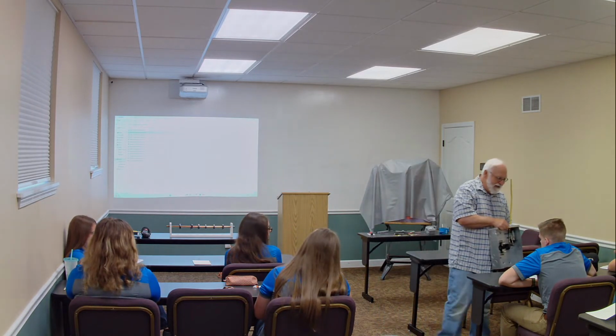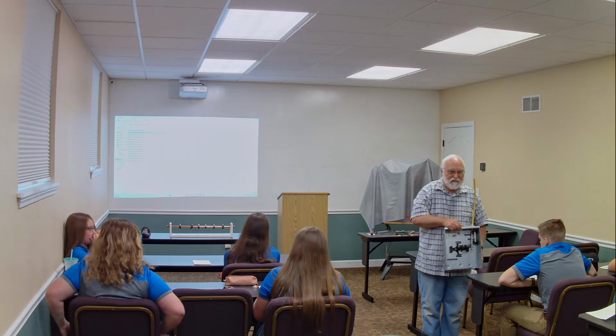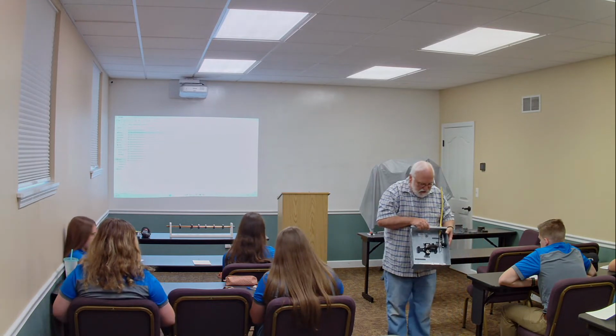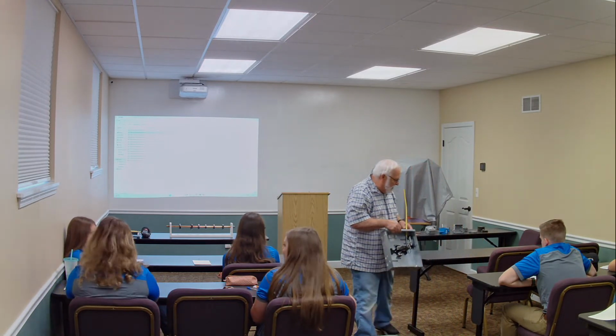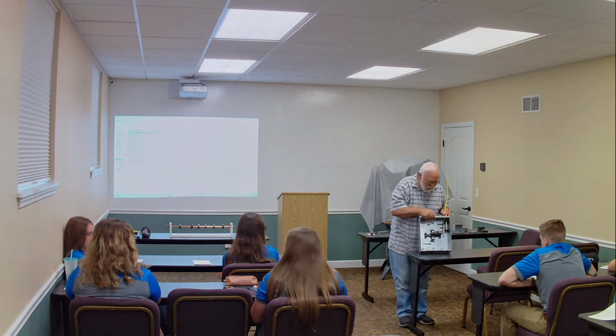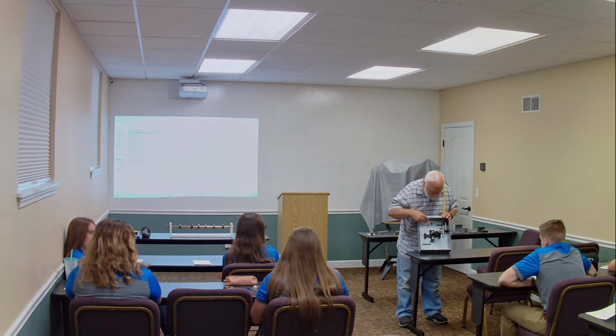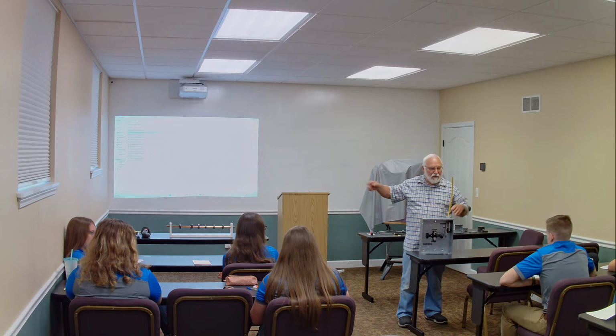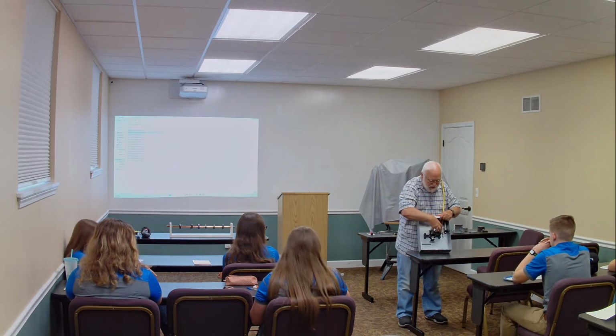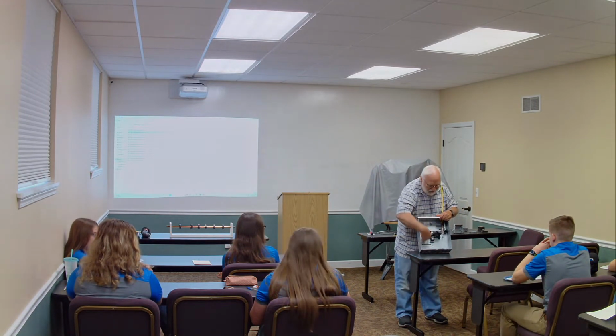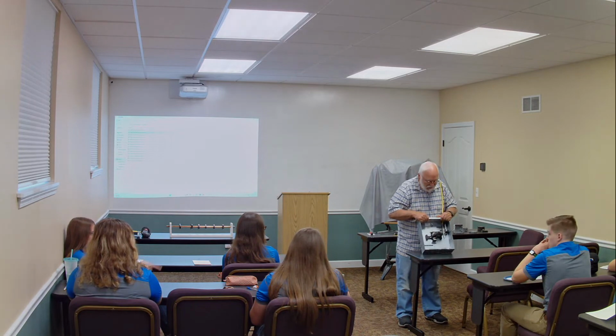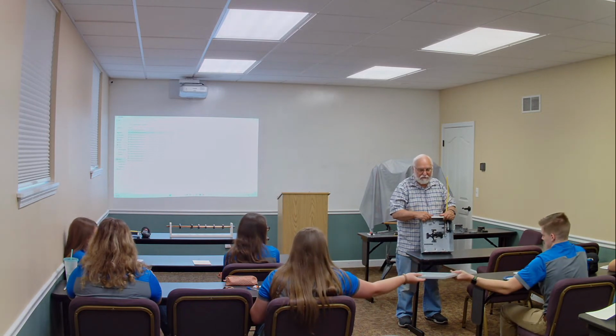Okay. So how is this different than the main breaker? This is different from a main breaker panel because this is a sub panel. Main breaker panel would have the main lugs. Remember, they had the two big lugs. They had a main breaker up here, and then they had bus bars. This does not.